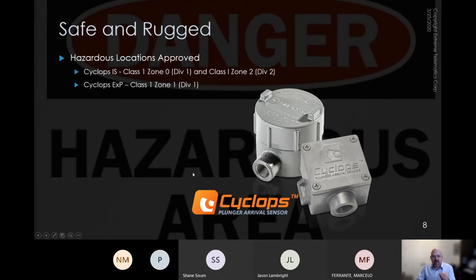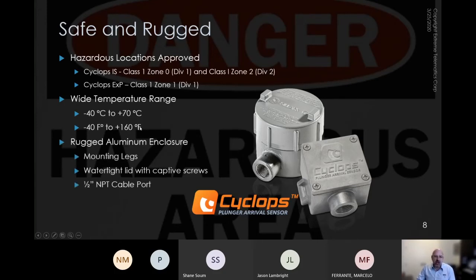We built sensors that have the best hazardous locations approval, whether that's Zone 0 or Div 1 for the intrinsically safe version, or a Zone 1 explosion-proof variant—there are a couple of different variants. We have a very wide temperature range because we use industrial components: minus 40 Celsius or Fahrenheit to plus 70 Celsius or plus 160 Fahrenheit, thanks to these high-grade components. We've put them in very rugged enclosures—the IS has mounting legs, captive screws in the lids so they don't fall out, and a half-inch NPT cable port so you can use a variety of connectors. We've just tried to make a great product that encompasses this technology.